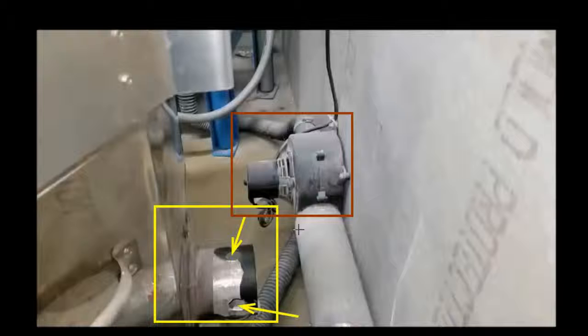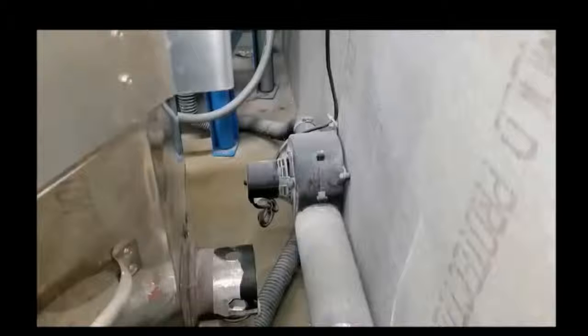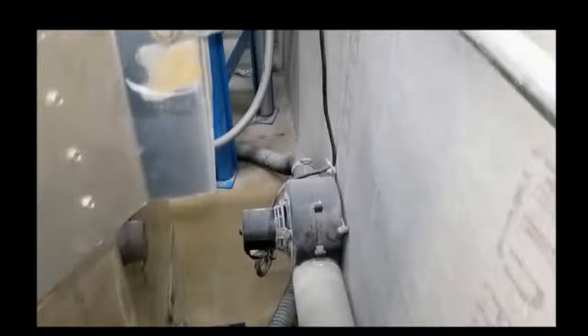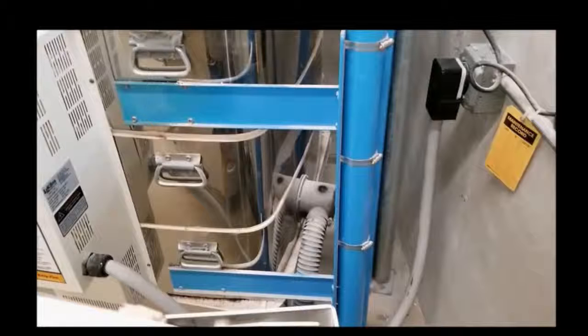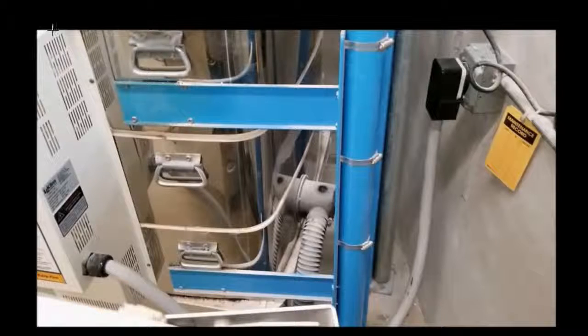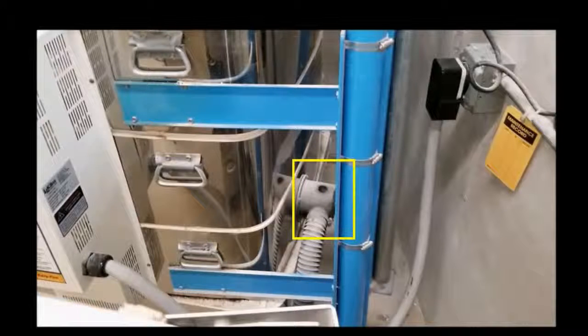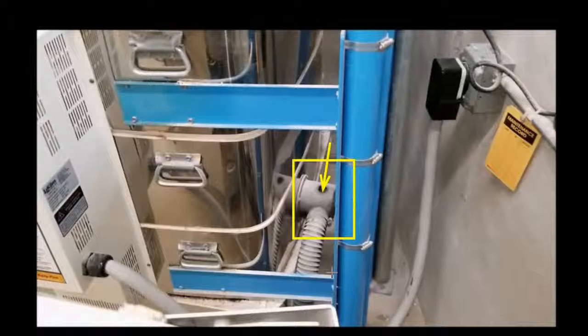So as you can tell, if you look down here, you'll see they have some type of plastic tubing. And of course, the plastic tubing is probably not going to survive real high-temperature situations. And if we scoot along here a little further, here's our second pickup on our second kiln. And again, important part is they bring in enough room air in this manifold to make sure that this plastic hose won't melt and they won't burn out their exhaust blower.